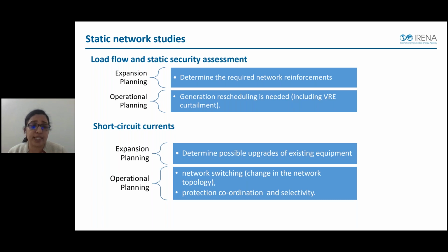So in case of operational planning, the recommendation would say generation rescheduling is needed, including VRE curtailment. The same thing is applicable for short circuit studies. In case of expansion planning, it would recommend to determine possible upgrades for existing equipment. And in case of operational planning, the recommendation would be for network switching or changing the network topology and review the protection coordination. Next slide, please.